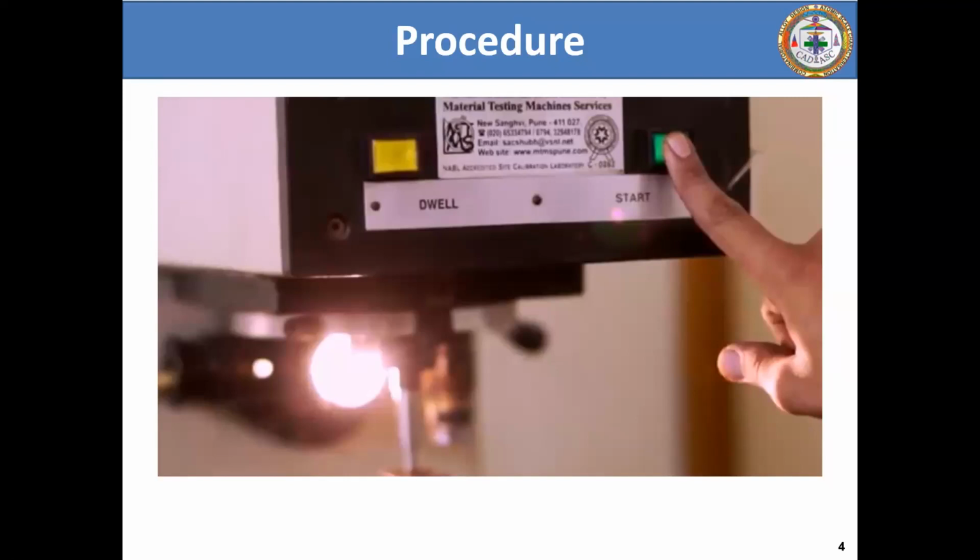Okay, so fine. Let's progress. So what do you mean by dwell time? Dwell time is nothing but the time for which indentation is performed in any material. So this is called a dwell time. In my experiments, generally I keep the dwell time around 20 seconds. It again depends on how accurately you want to do the indentation. If you want to get more and more accurate values, you have to do the indentation for a bit higher time.